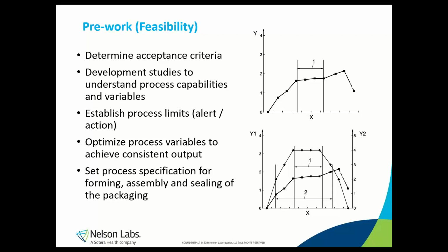ISO 11607 says you need to have a process specification for the forming, assembly, and sealing of the packaging. Forming specifications could be as simple as documenting the preformed pouch that you'll use, including the size, the materials, and the vendor or part number. If you're forming the packaging in-house from sheet or roll stock, you would want to specify the materials used, including the thickness or the material grade and the specifics on the material composition, in addition to specifications on the final packaging, including size and shape and seal width.